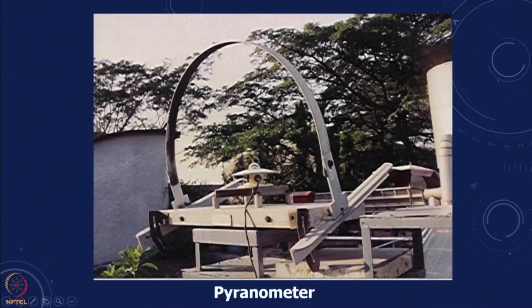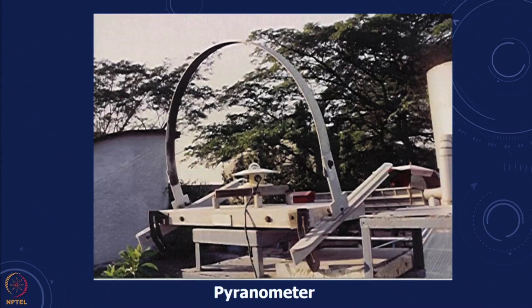You also have what is known as a pyranometer, and the pyranometer can be used for measuring diffused radiation or total insolation. There is a blocking sheet which can be used to block the direct, and then what is measured becomes only the diffused. If we remove this, we get the total insolation on a horizontal surface — the global horizontal insolation. So the direct plus diffused gives us the horizontal insolation.